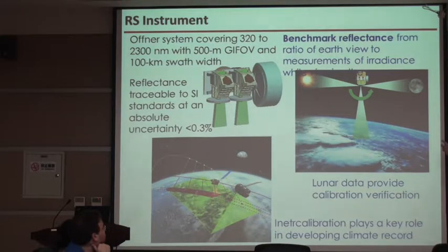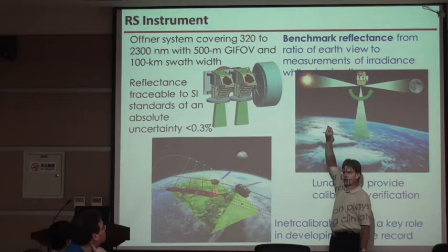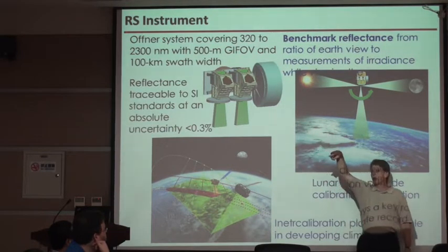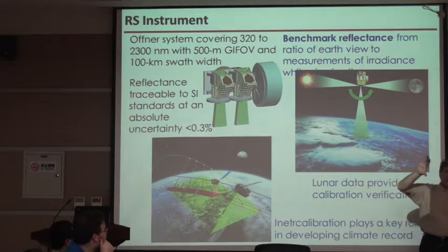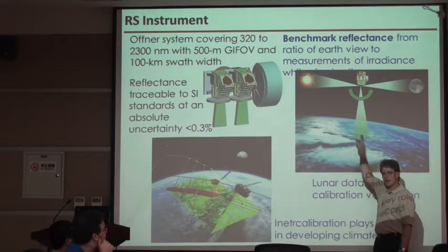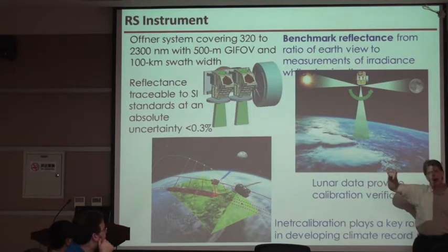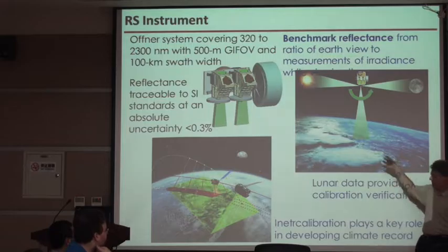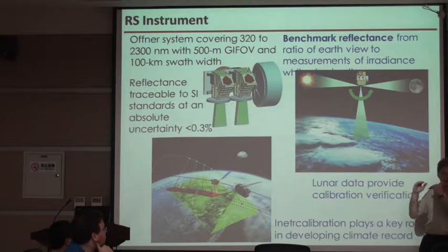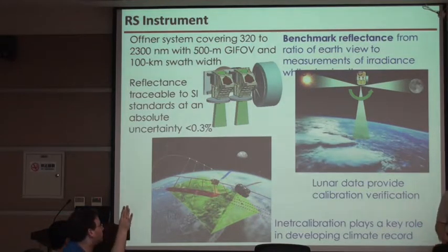And when we look at the moon, we do not need those attenuators. So if the sensor shows no degradation looking at the moon, but shows degradation looking at the sun, then we know it's the attenuators that are the problem, and we have to change our error budget and do a recalibration. But if they both show the same degradation, then we're confident that it's the detector package, and that gets taken into account, and then we look at the Earth and do the ratio. The ratio gets rid of that degradation. So we should be at 0.3% end of life.